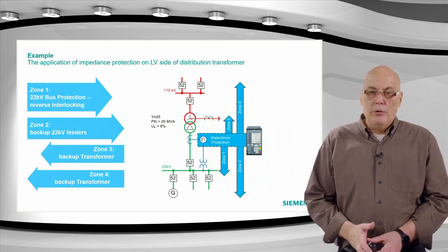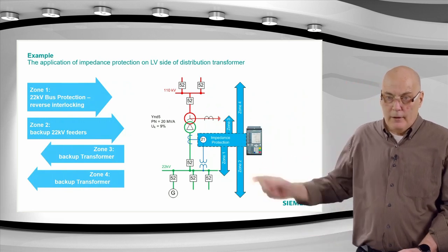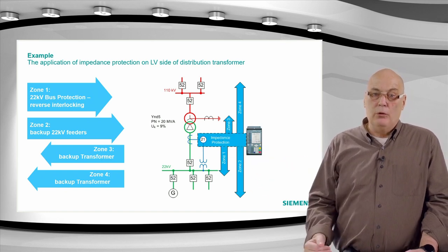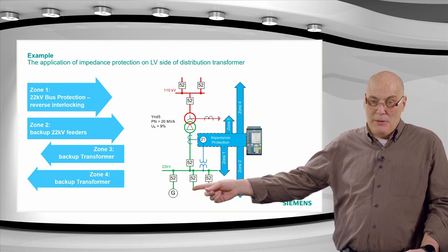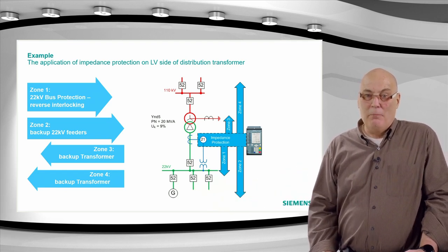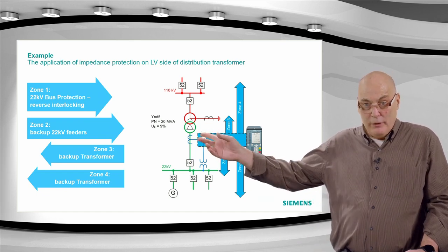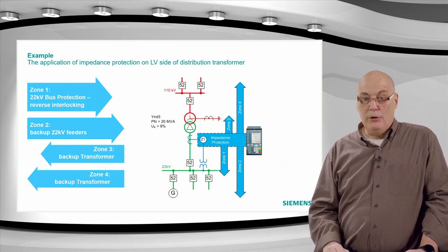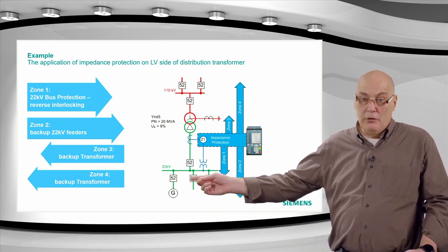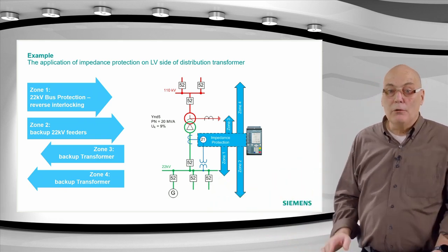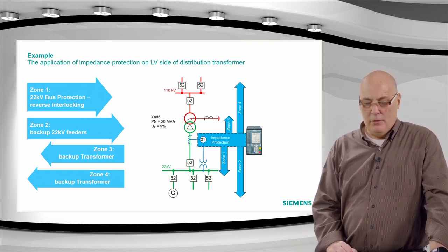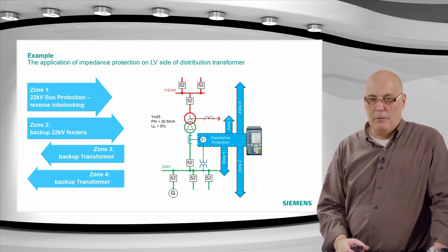An example I'm going to use to show this is what you see here, a typical medium voltage transformer. This example is 20 MVA, and you'll find that typically, especially to what we see in the bottom here, the renewable generations, often these transformers are reaching their limits, and nowadays often in this environment where it used to be 20 MVAs, one goes up to 40 MVA to make allowance for not the consumption down here, but the generation in some sense, which creates new difficulties in applying protection. But let's go for it step by step and not get ahead of myself, as I sometimes do.